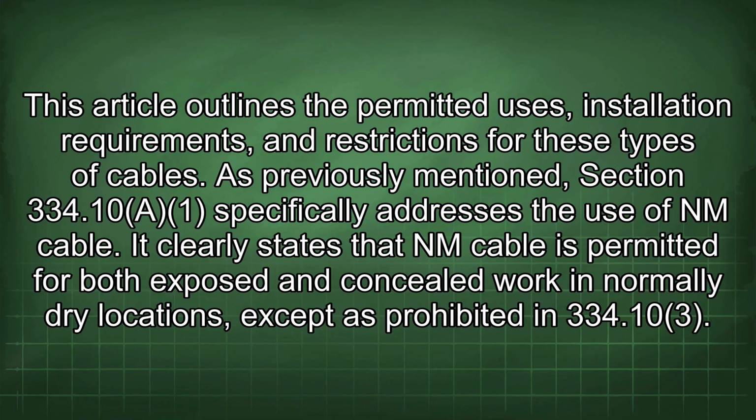As previously mentioned, Section 334.10(A)(1) specifically addresses the use of NM cable. It clearly states that NM cable is permitted for both exposed and concealed work in normally dry locations, except as prohibited in 334.10(3).